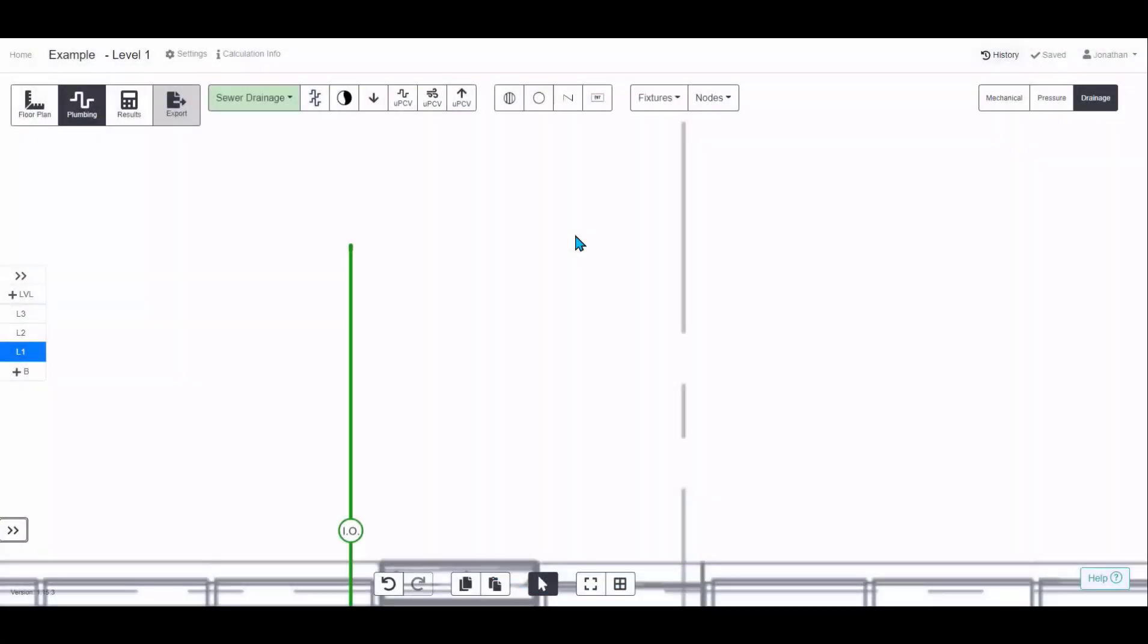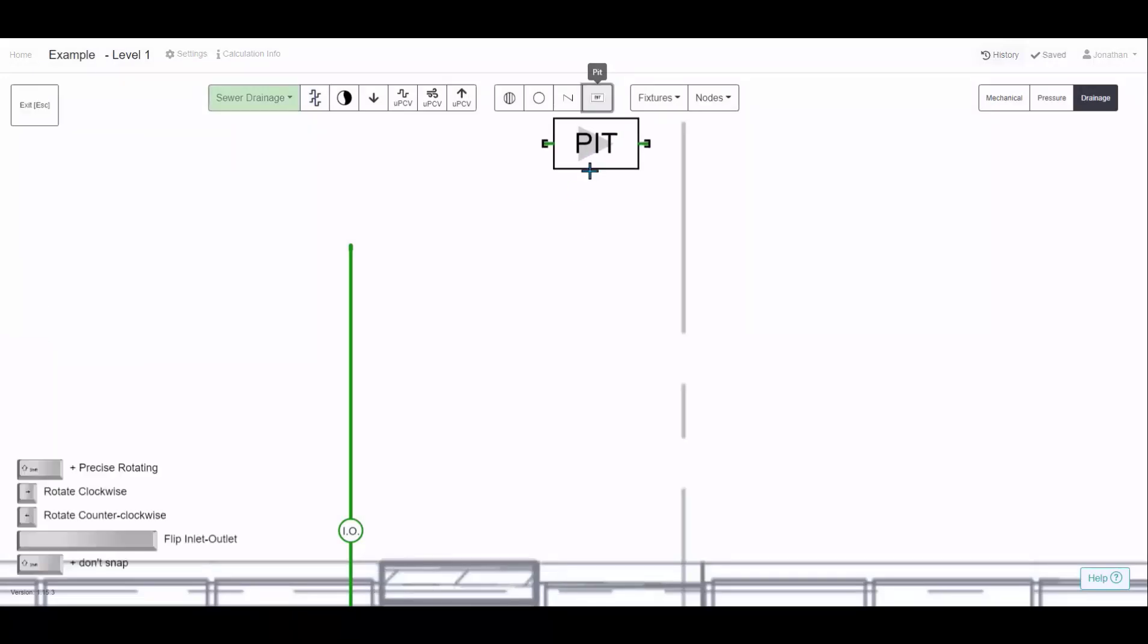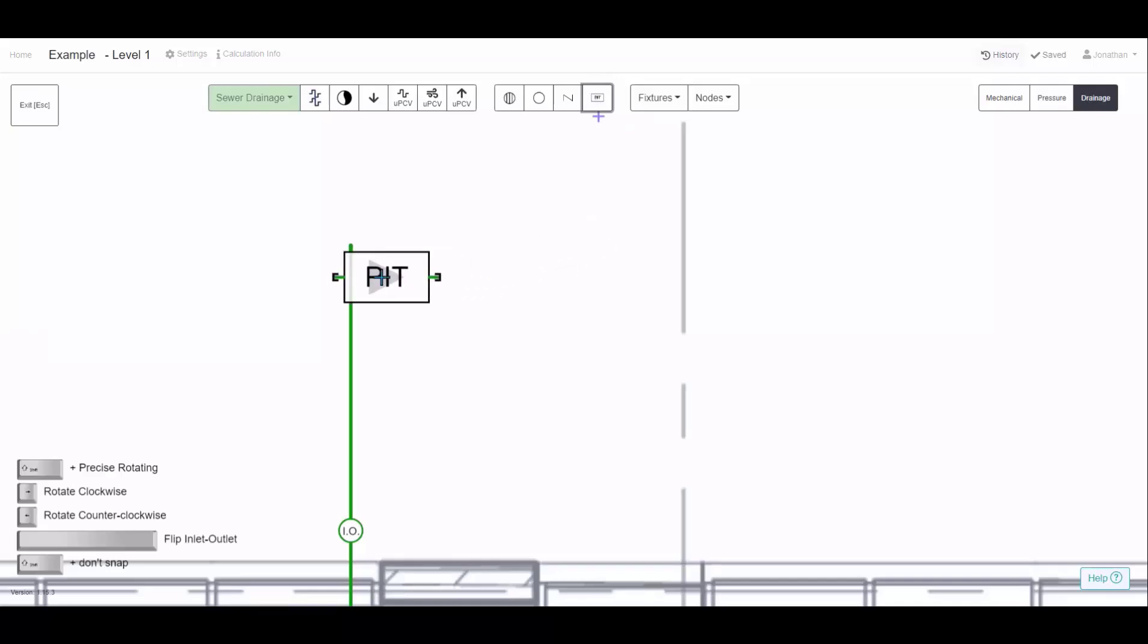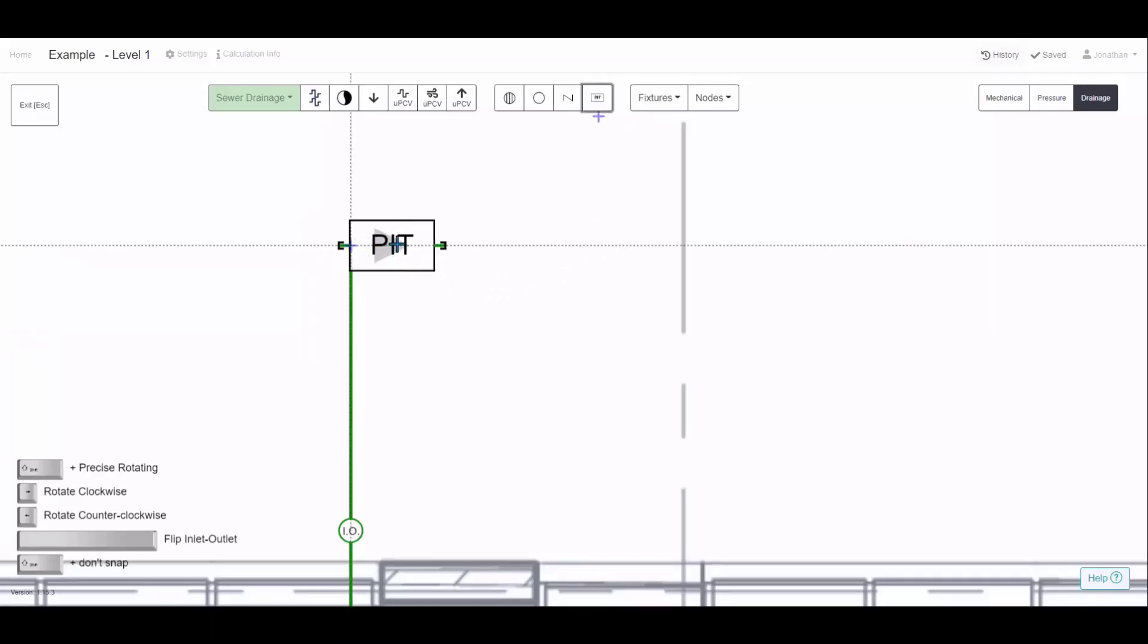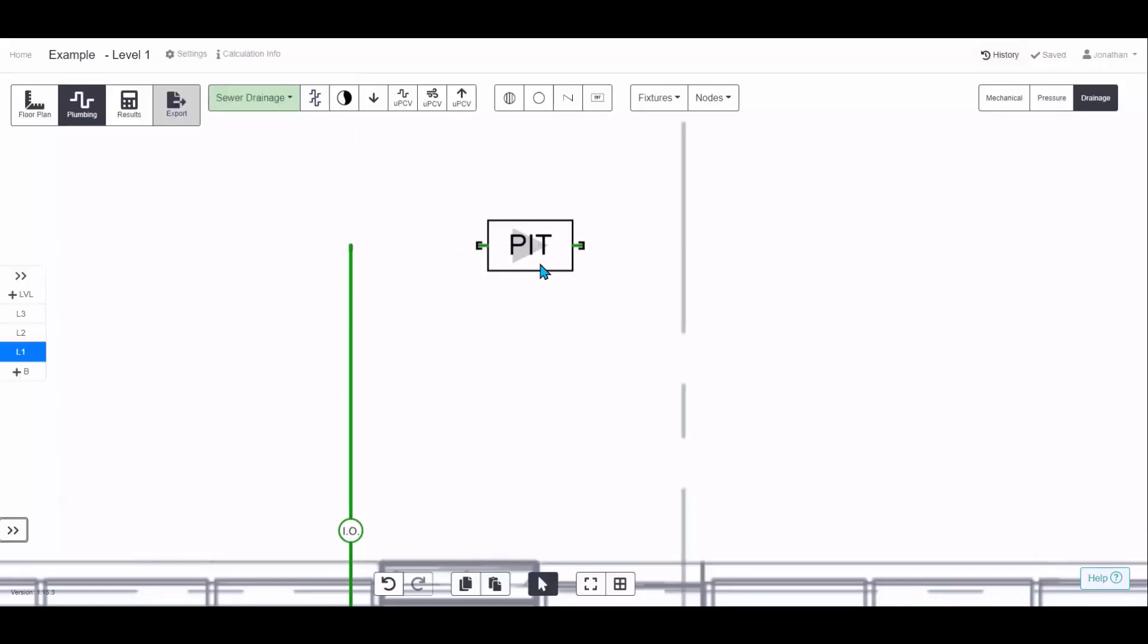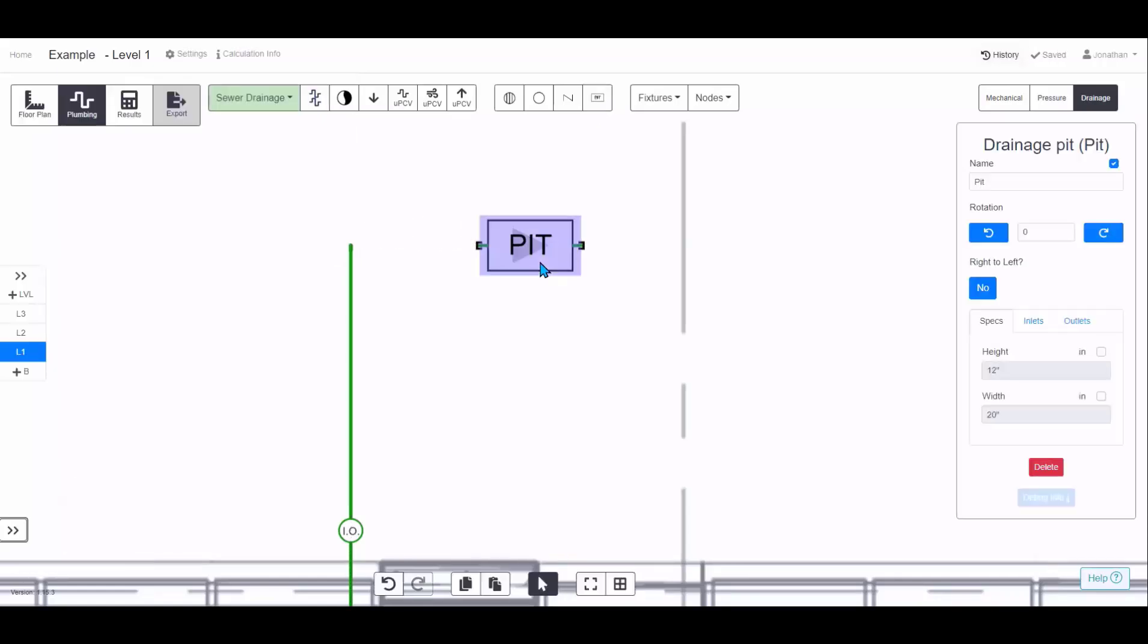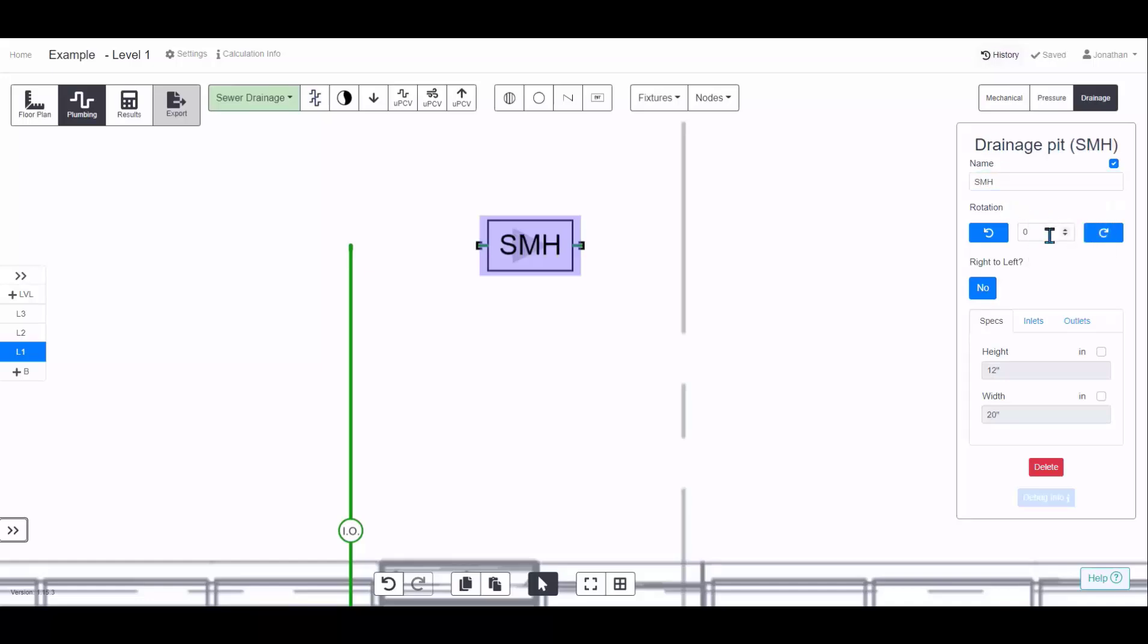To add a pit or a tank to your wastewater design, you can choose it from the toolbar here, and click wherever you'd like to locate that. If you'd like to align it with a pipe you've already drawn, hover over the end of it, and then as you move away, it will snap to that line. Then in the properties of the pit, you can change the name. So you could call it, say like a dilution pit, grease arrestor, sewer manhole for example. From there, you can rotate it, you can flip which direction you want the flow to go.